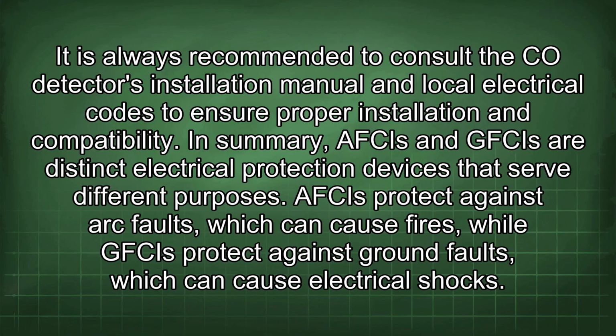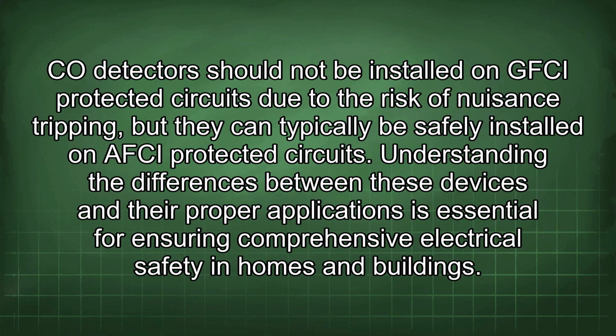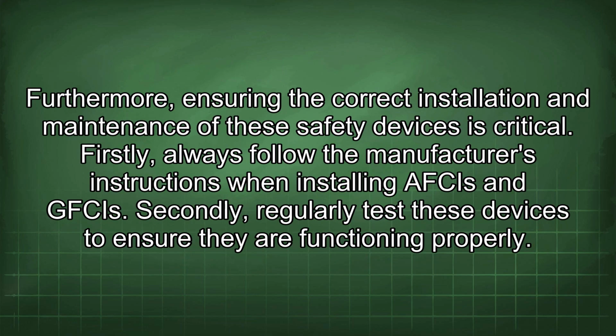AFCIs protect against arc faults, which can cause fires, while GFCIs protect against ground faults, which can cause electrical shocks. CO detectors should not be installed on GFCI protected circuits due to the risk of nuisance tripping, but they can typically be safely installed on AFCI protected circuits. Understanding the differences between these devices and their proper applications is essential for ensuring comprehensive electrical safety in homes and buildings. Furthermore, ensuring the correct installation and maintenance of these safety devices is critical.